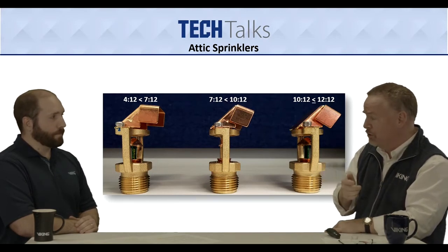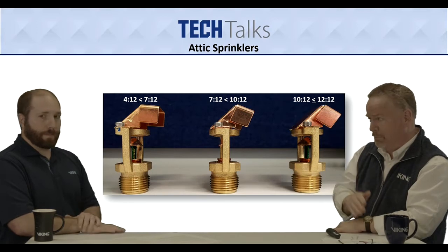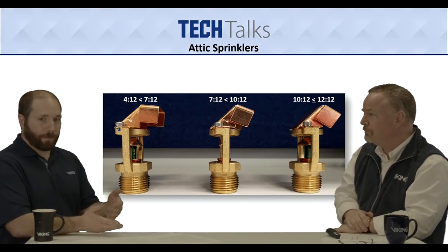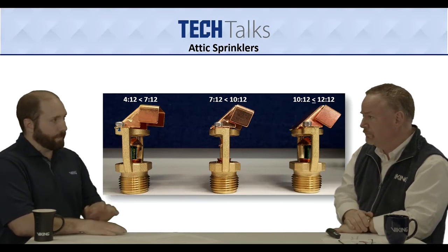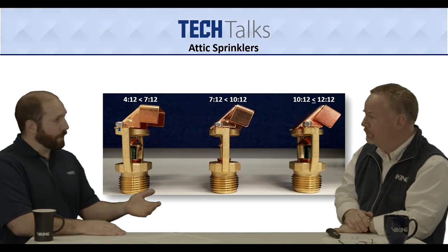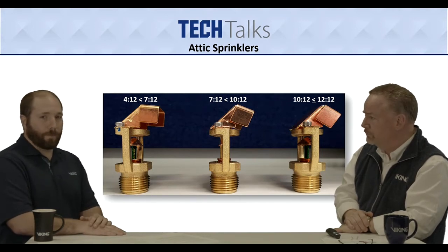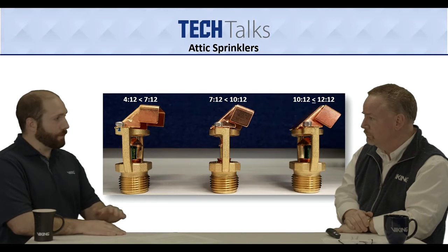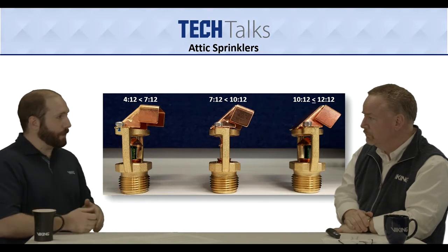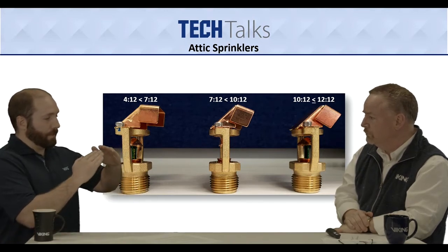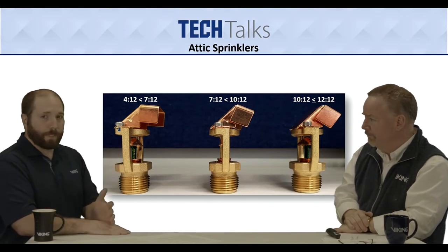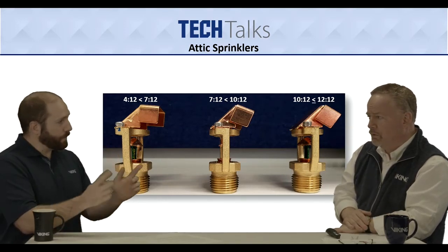So this is also a vertical installation, upright only? Yes, it is. So the sprinklers are going to be ordered based on the pitch of the roof. Could you do a multiple slope? Sure. We could do a 4 and 12, 7 and 12 on one end, and maybe 8 and 12 on the other. So if you had a multi-slope roof, you could position single directionals that way as well.